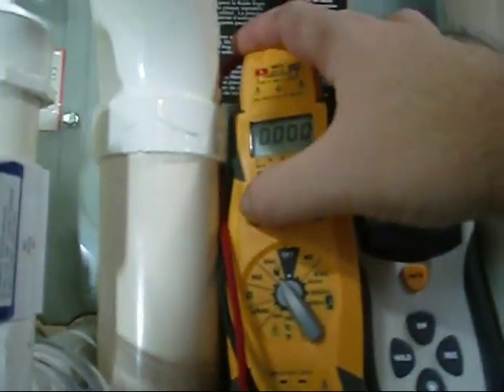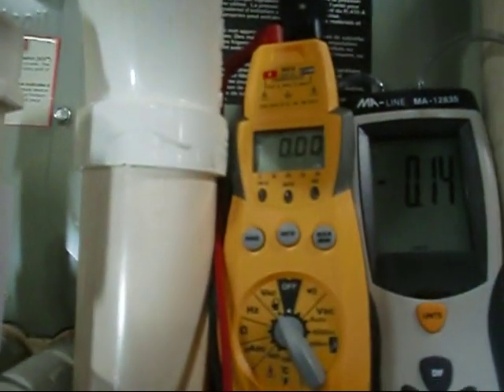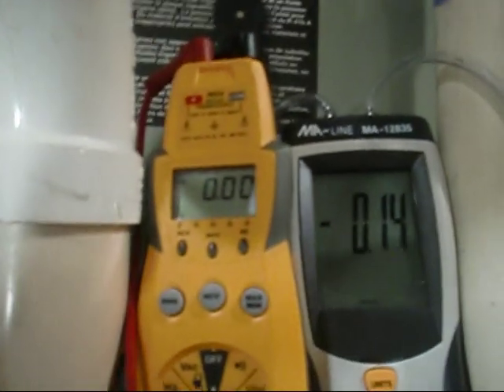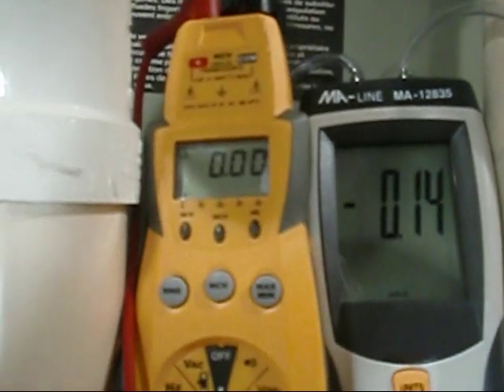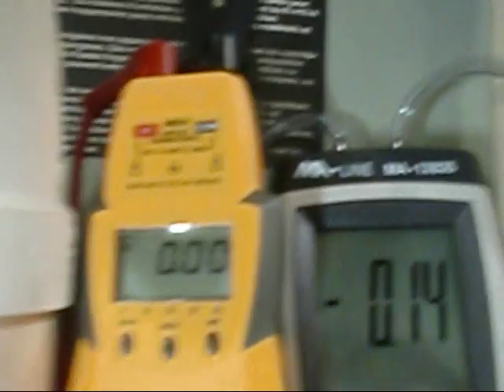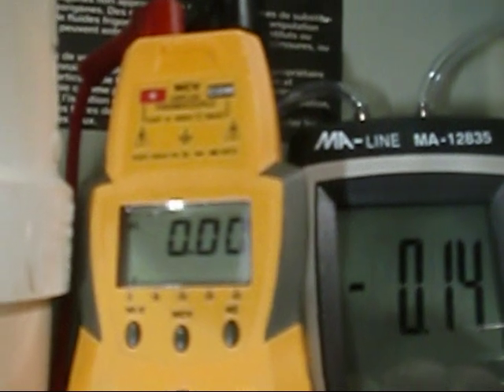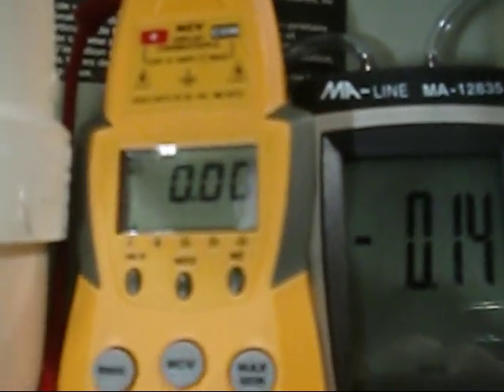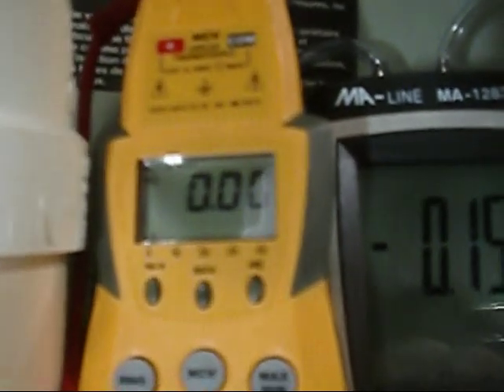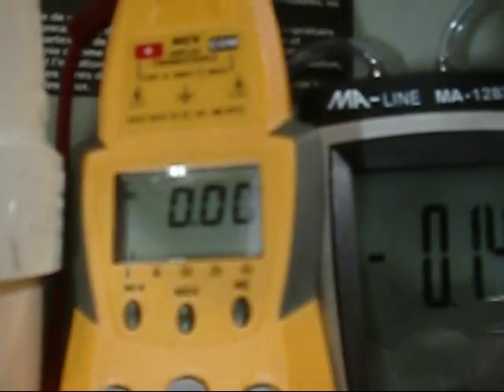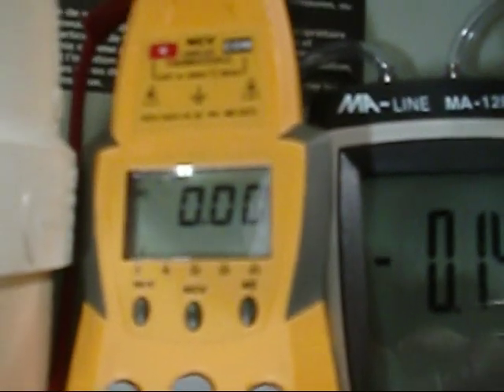We've got our spade terminals back onto our respective terminals on our pressure switch here. And we've got our Fieldpiece hooked up, we've got the alligator clips on there. And I reckon we're ready to rock. Let me set my range here. Now, this is going to be quick. So you're going to have to keep a quick eye on this now. Once I hit that switch, we're going to read low voltage. And, you know, commonly called in the field here, we'll say we've got 24, we've got low voltage. Well, this thing could read 24, 25, 26, 27, 28. But low voltage nonetheless.